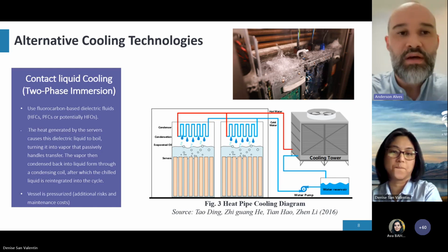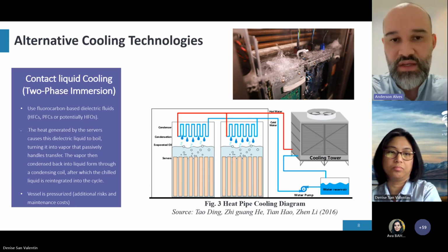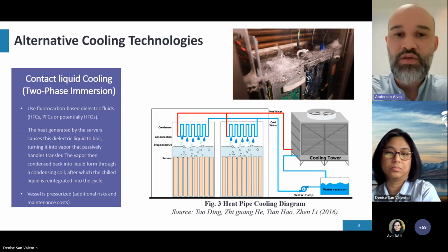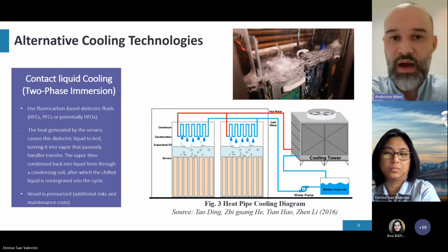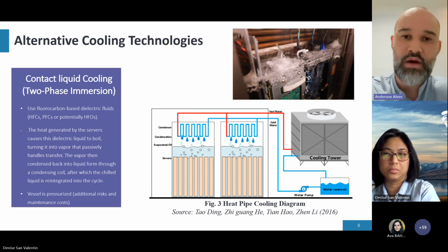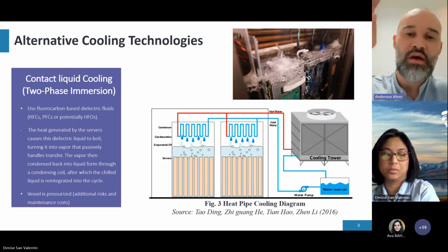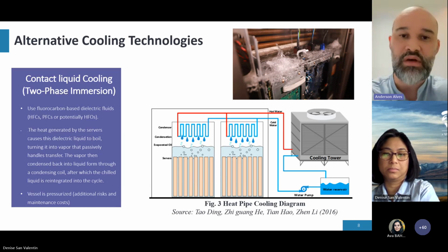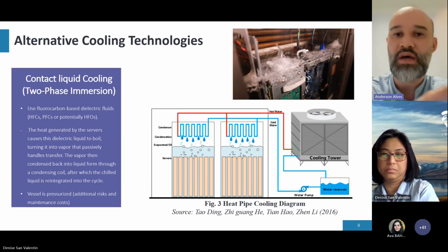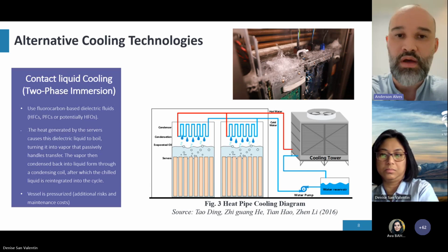So the first one, which is largely promoted by, for example, some big techs today, is two-phase immersion cooling. Basically, it's a pressurized vessel where this dielectric fluid enters directly into contact with the servers. The servers heat up, and this liquid will also heat up and evaporate, and the vapor will be caught by a condenser unit inside the pressurized vessel. This condenser unit will cool down the vapor, which will condense as liquid again. So this process continues inside the pressurized vessel. And outside you will have a standard water system that circulates through a cooling tower to cool down the condenser.